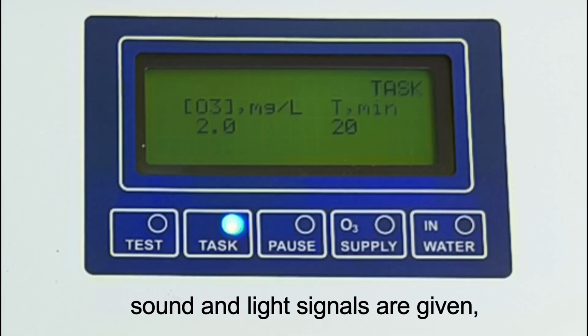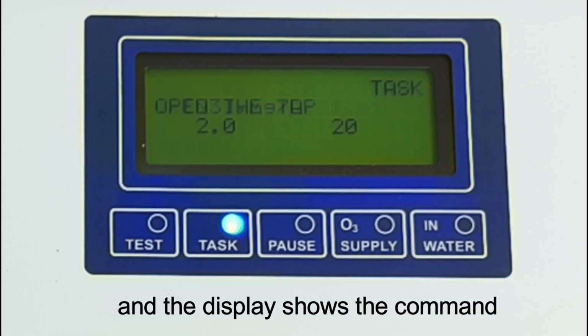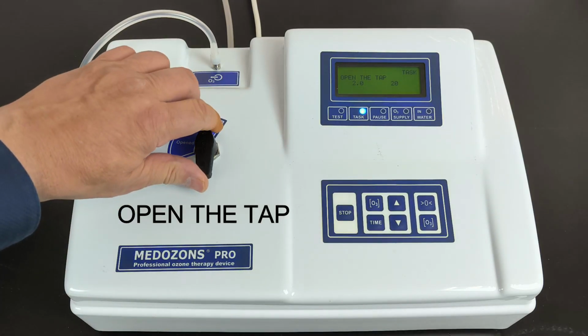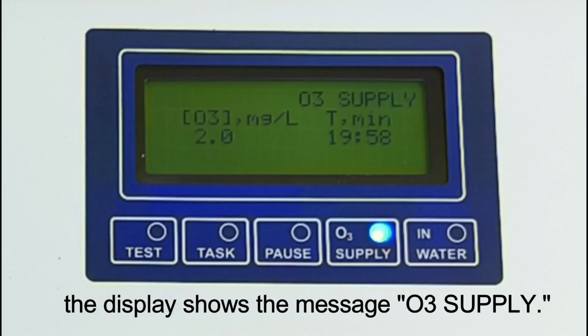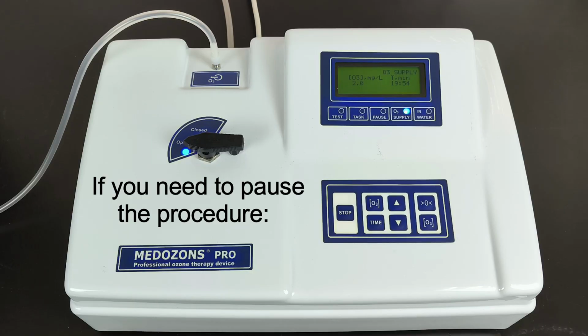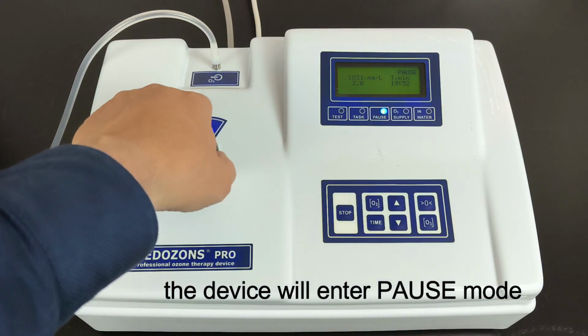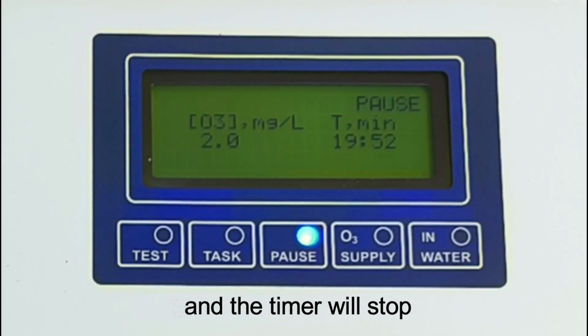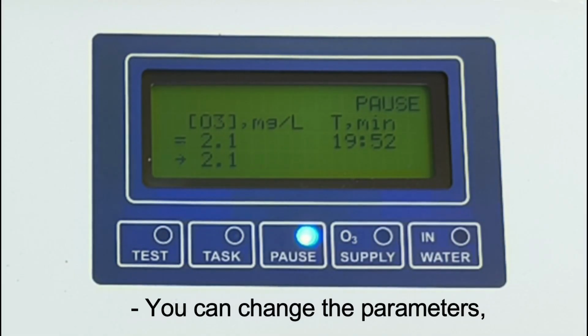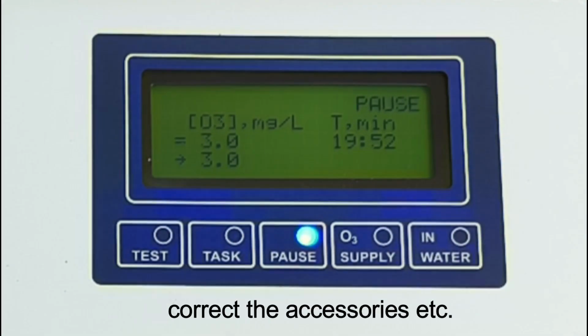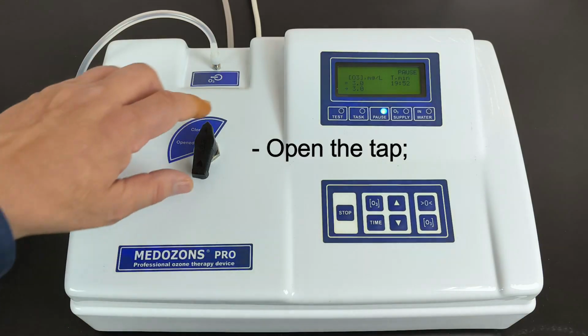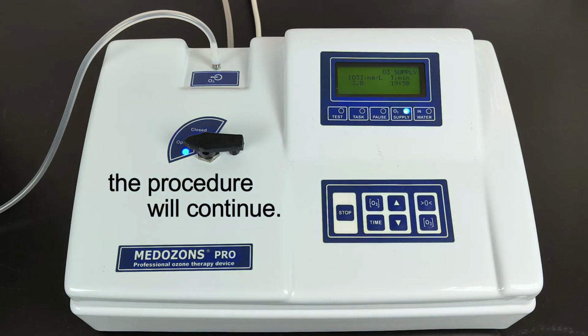Sound and light signals are given, and the display shows the command open the tap. Open the tap. Ozone supply begins, and the display shows the message O3 supply. If you need to pause the procedure, close the tap, the device will enter pause mode, and the timer will stop. You can change the parameters, correct the accessories, etc. Open the tap, the procedure will continue.